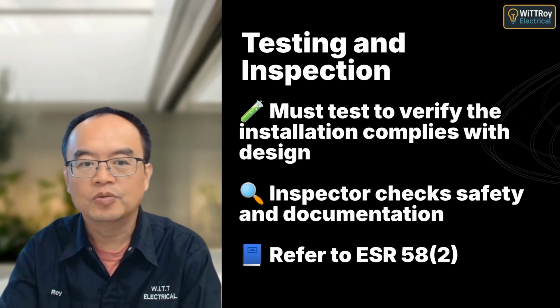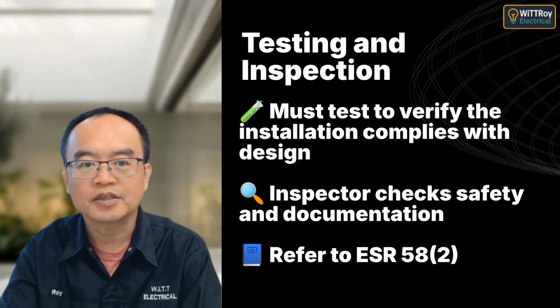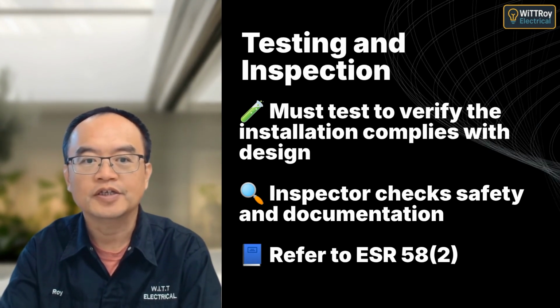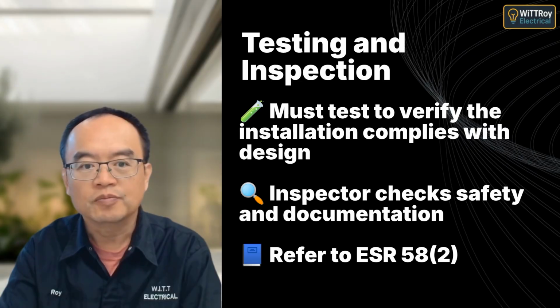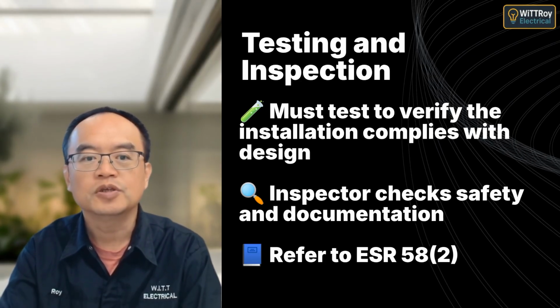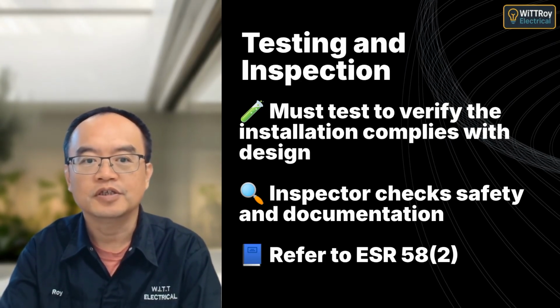An installation built to a certified design must still be tested and inspected. According to ESR 58.2, this inspection ensures the installation is electrically safe and meets the intent of the certified design.